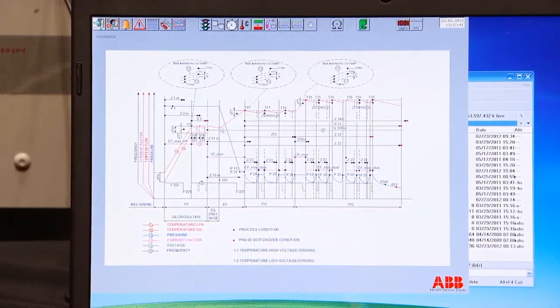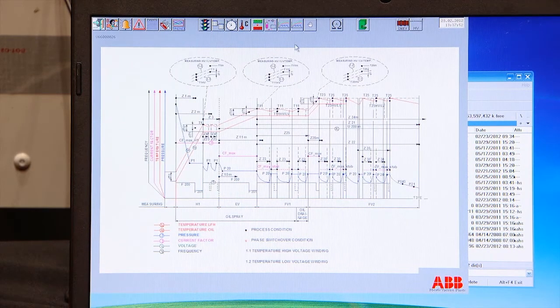Between here and here, you see it says oil drainage. Normally you're running oil spray circulation. Then it looks more like this picture. You have two process pictures: one with oil spray and one without oil spray. You're heating up, doing your stabilization. Evacuation is only heating up. There's no oil drainage in this one. In the other one, you have an oil drainage phase where you're draining the oil from the transformer tank. So you're heating up to your fine vacuum value and doing the next stabilization phase.